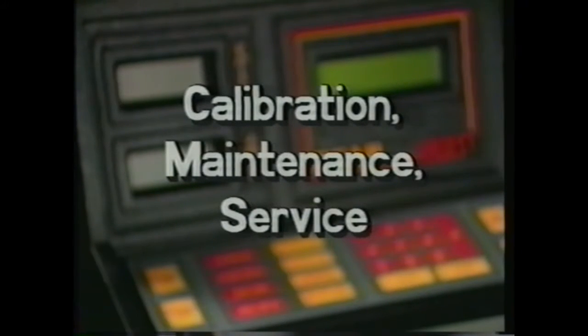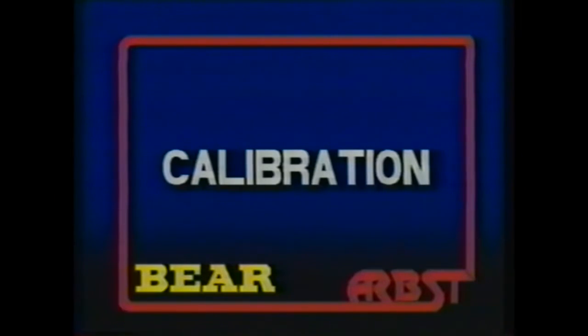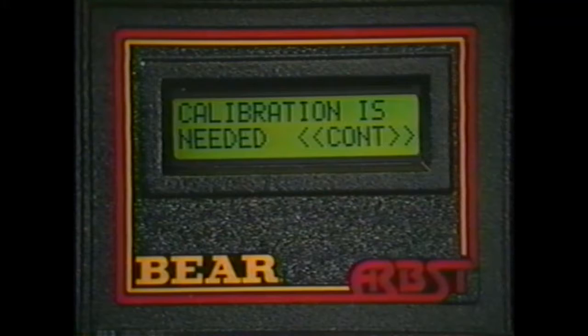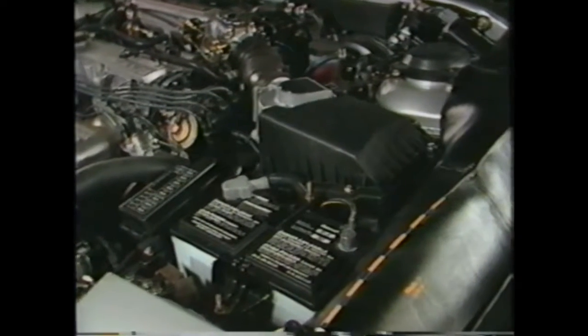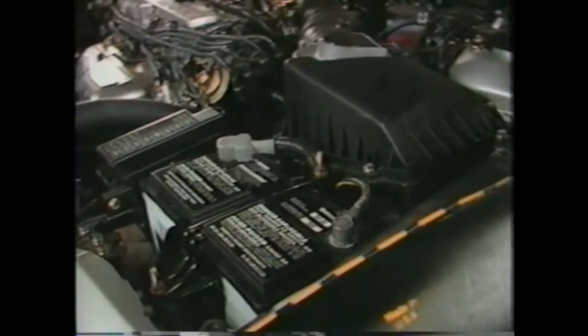Your ARBST tester has an easy-to-run procedure that enables you to calibrate all the tester's leads. When you turn the tester on, it automatically checks to see whether calibration is required. If it is, the display says calibration is needed. In order to perform calibration, you need a good, fully charged 12-volt automobile battery.